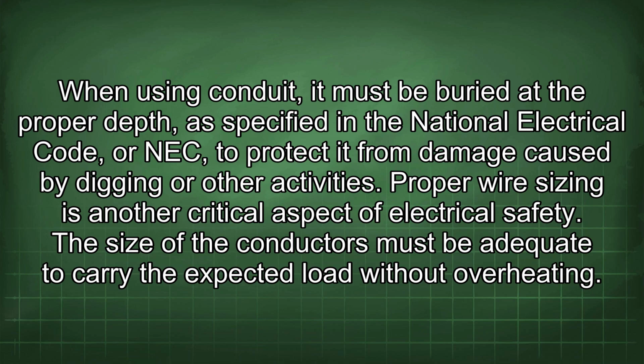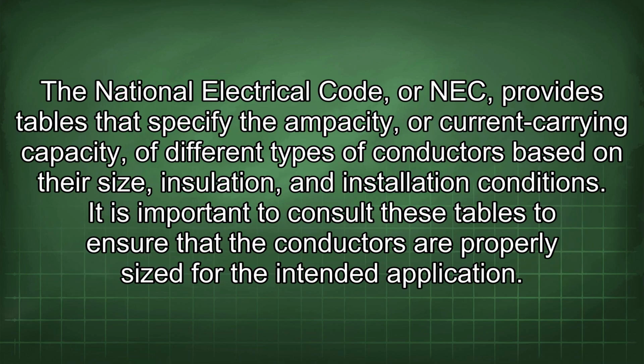Proper wire sizing is another critical aspect of electrical safety. The size of the conductors must be adequate to carry the expected load without overheating. The NEC provides tables that specify the ampacity, or current carrying capacity, of different types of conductors based on their size, insulation, and installation conditions. It is important to consult these tables to ensure that the conductors are properly sized for the intended application.